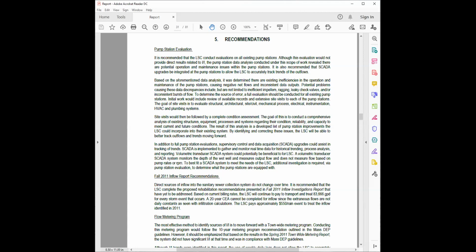The bells and whistles could be determined as you go along, but it would make sense to start by setting a node up likely at the DPW. The initial upfront cost would be more for setup, since you'd need a server and a node. Communications is probably the biggest thing - you'd need a radio path study to figure out the right communication capabilities, whether you need elevated antennas, where your polling master is, or if you need a repeater. That'd be part of the evaluation on the front end.